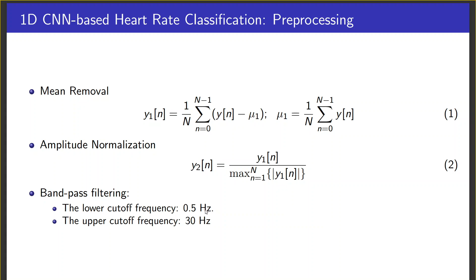And the bandpass filtering stage helps to reduce the effect of different types of artifacts and noises present in the signal. The prominent QRS complex lies between 0.5 Hz and 30 Hz, and we are setting the lower cutoff frequency as 0.5 Hz in order to remove the baseline wander, patient movement artifacts and respiration artifacts present in the signal below 0.5 Hz, and we are setting an upper cutoff frequency in order to remove the power line interference and muscle noises from the signal.